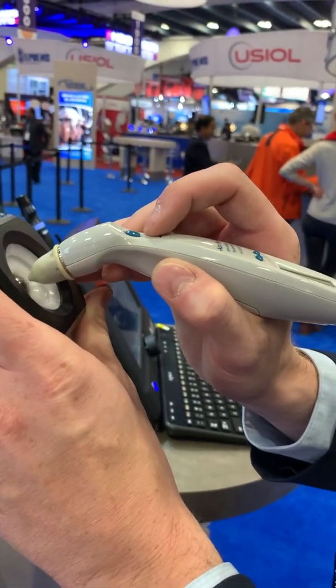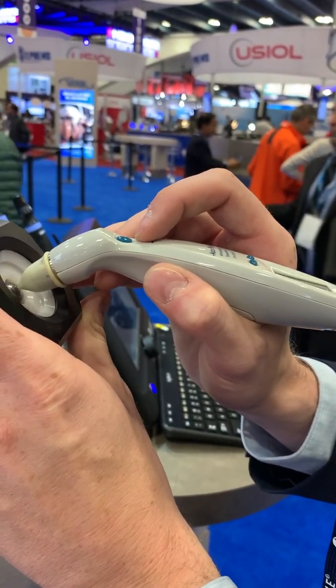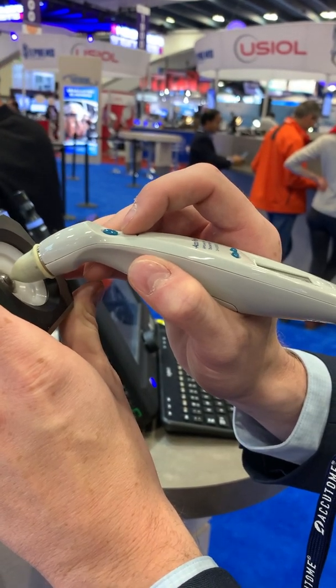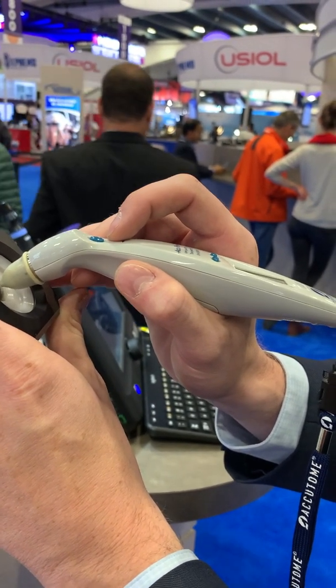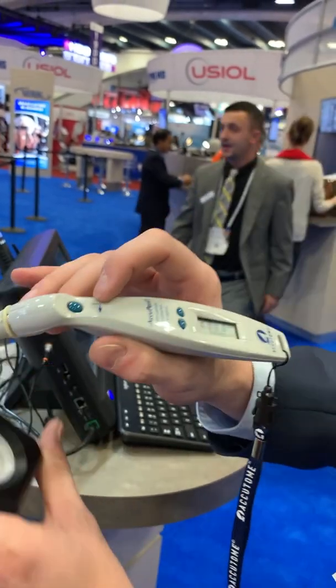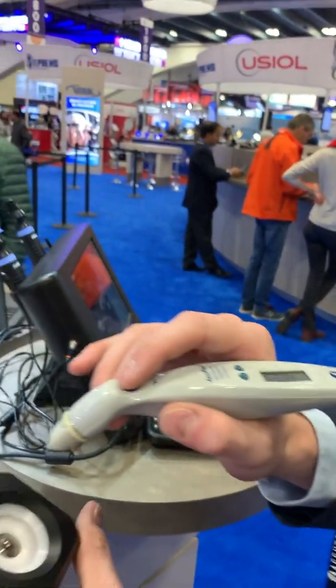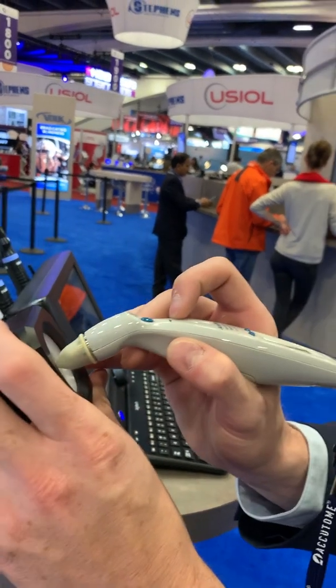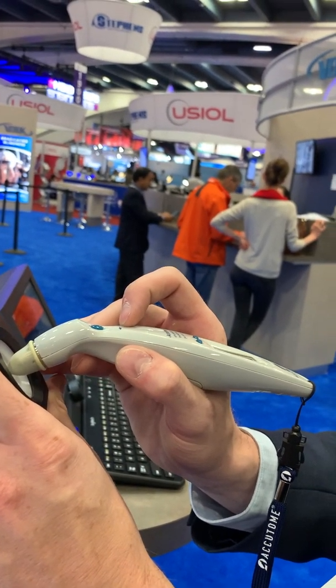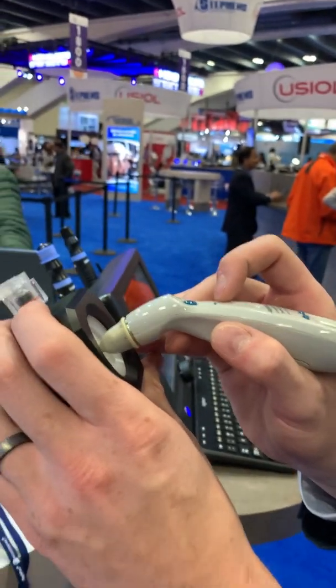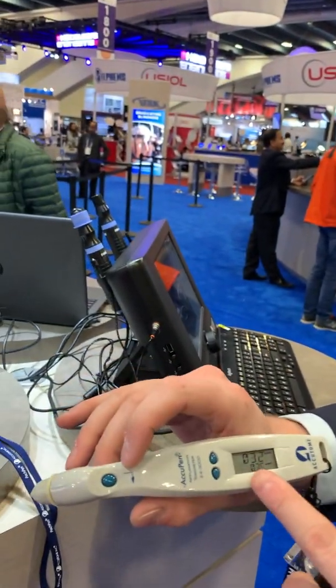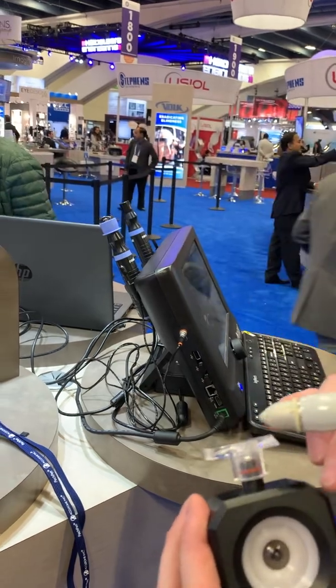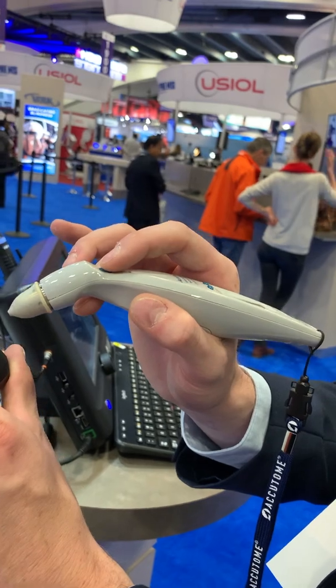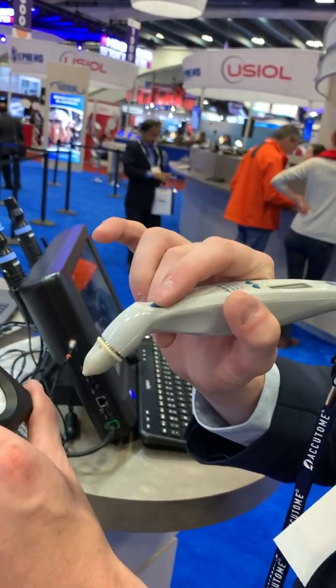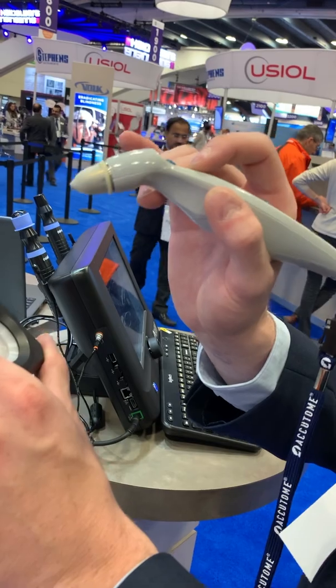So I've taken 2 measurements in about 5 seconds here. Because pinching the cornea many times will trouble the patient. So we're just slowly getting more measurements as we're going through. If we pinch the cornea only 2 to 3 times, can we get the result? Most likely not. You're going to need a few waveform patterns in order for it to match up. So looks like we're reading about a 30 on this side. It's probably a little overinflated. Each one of those is taking a corresponding waveform pattern, and once we get 2 waveform patterns that match up, we'll get a reading. So it's just going to be a few taps on the eye each time.